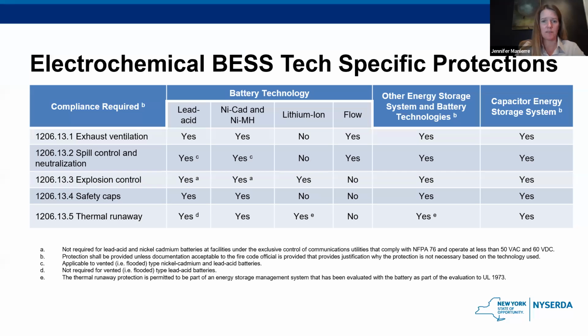Explosion control, on the other hand, is required for lithium ion batteries because if something does go wrong and they start to overheat or catch fire, at that point, lithium ion batteries can start emitting explosive gases. So they definitely need explosion control features. Now, an option for explosion control for lithium ion might be some sort of exhaust ventilation, but they don't need the exhaust ventilation just as a default operating thing. So this chart just outlines which requirements apply to which types of batteries, basically.